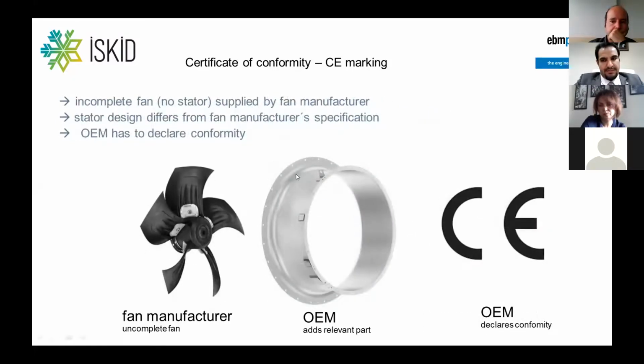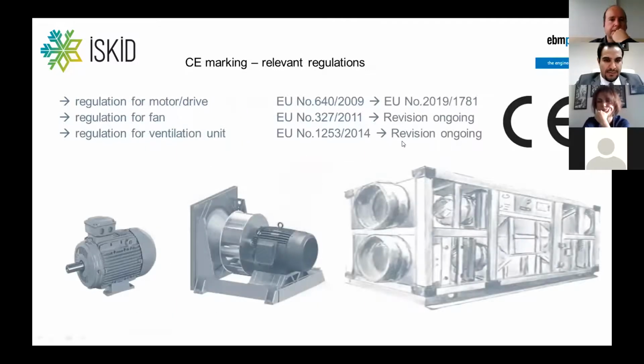But if the fan manufacturer just provides the fan with the motor, and somebody else or the user later on designs their own stator, different from the data the fan manufacturer created, then the one who added the last part, the stator, to the fan is the one who has to declare conformity. So if the fan is not complete and is used by somebody else who makes it complete, then that one gets into the position of being the fan manufacturer and has the responsibility of declaring conformity.